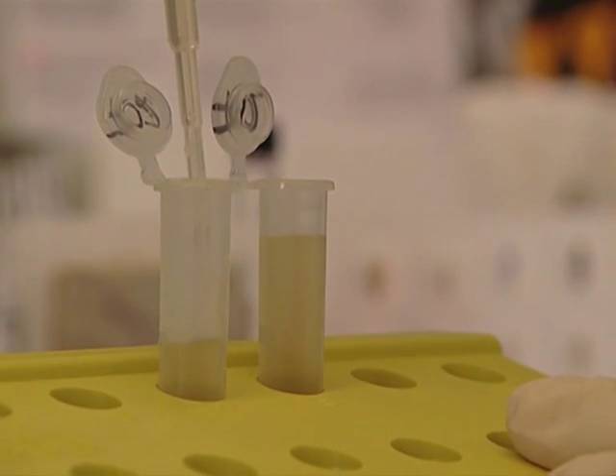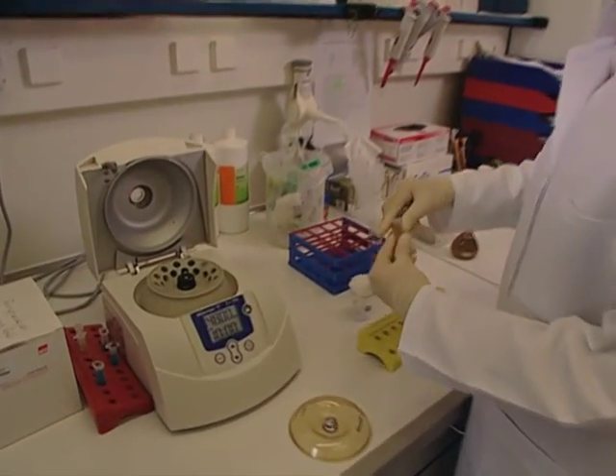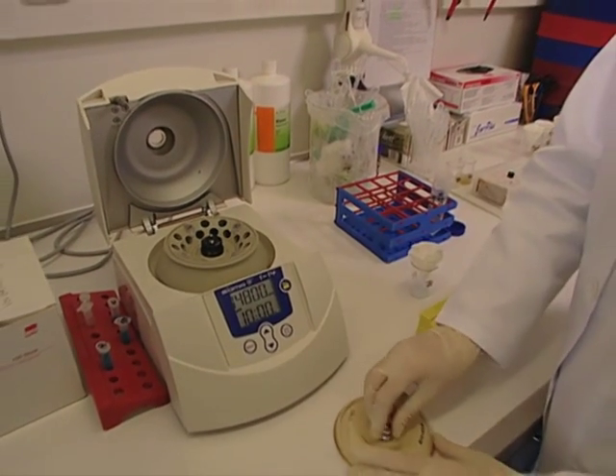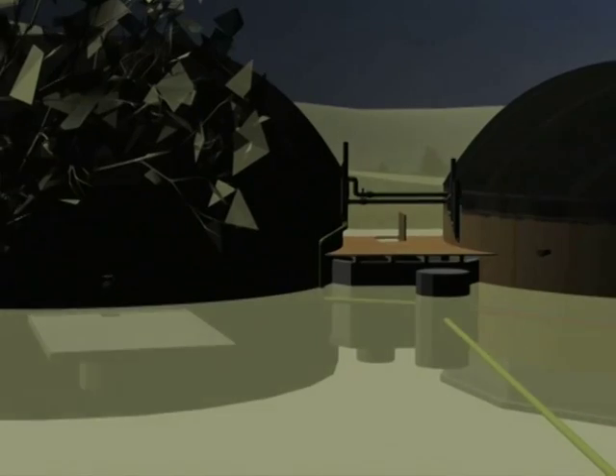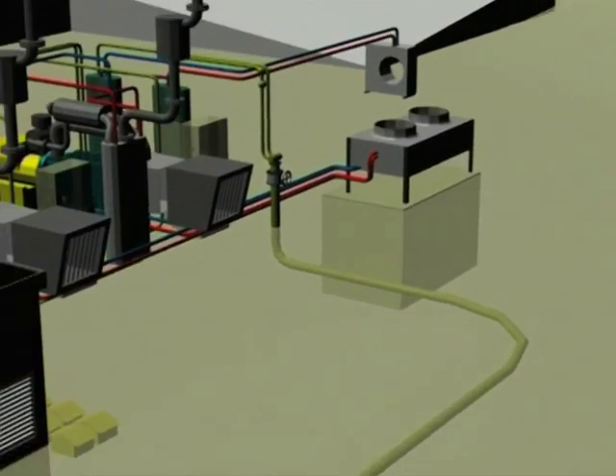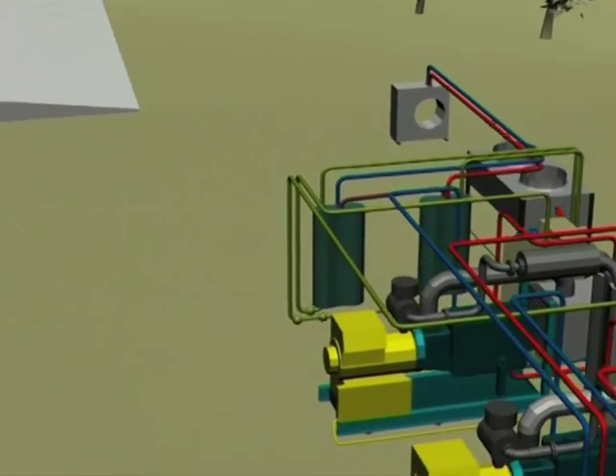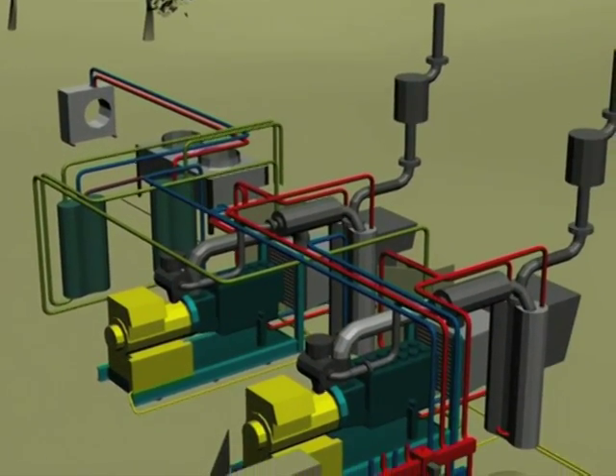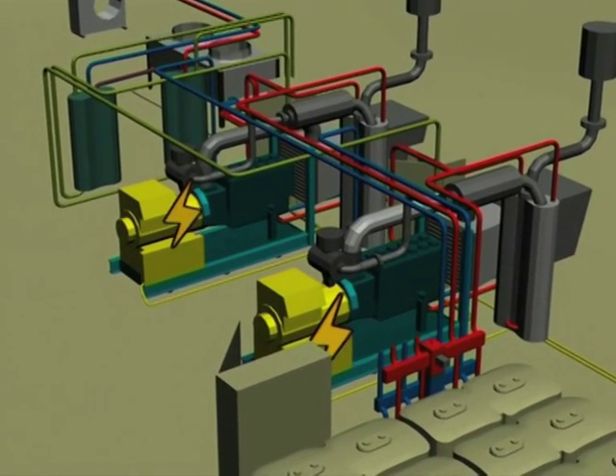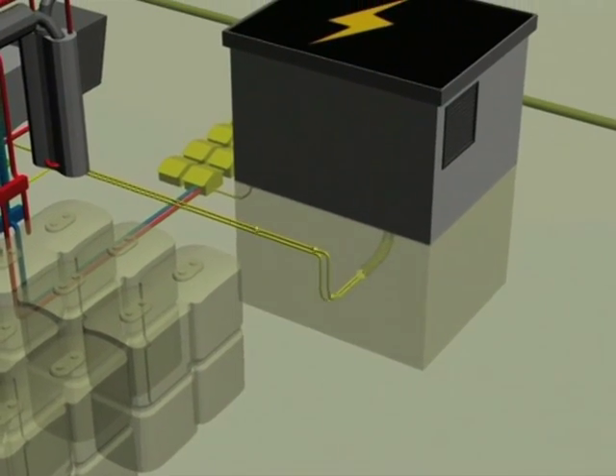We provide a suite of tests to understand the biology within the digesters. We work with operators of our plants to help them understand the importance of nutrients in their feedstock and how to maintain a good biology. Slurry and biomass are decomposed in the digester by anaerobic methane-forming bacteria. The warm moist biogas is cooled before reaching the engine to reduce moisture content, then compressed through an active carbon filter where H2S not dealt with by the natural process in the digesters is removed.